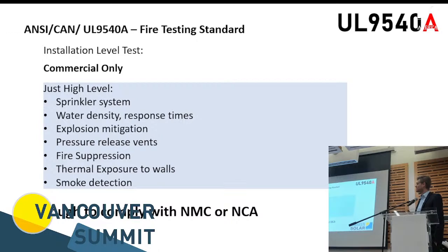The commercial, the installation level for commercial, that's pretty much for large-scale systems only. We don't want to go too deep into it. You have a whole bunch of other topics or other suppression systems that are introduced. If you cannot already meet at the cell level, the module level, or the unit level, then it becomes extremely complicated, extremely costly, because all of a sudden it's not just your battery module anymore. It's pretty much an entire electrical room with all kinds of safety things. And with the automotive NMC or NCA or NMA, it's very, very challenging to comply with those performance criteria tests on the cell, module, and unit level. That's why you see the big systems have all these prevention methods built in, and of course are much more expensive.